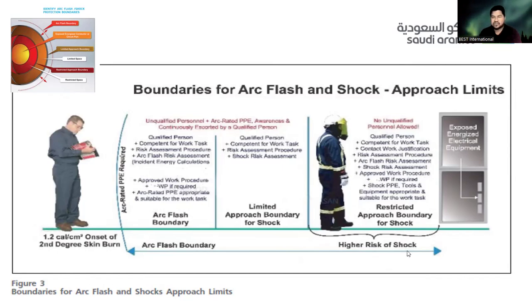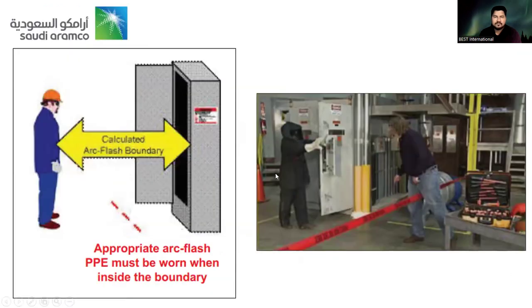There is an arc flash boundary and high risk of shock. See the PPE level here, where we have a high risk of shock because the person is directly exposed near energized electrical equipment. And this is a restricted approach boundary for sure. This is another self-explanatory one: we have to carefully define the line of fire, the boundary nobody should cross without a proper permit, proper PPE and guidelines, because in electrical systems there must be a procedure. The procedure should be shared and training must be conducted. Later, periodic inspections to evaluate effective implementation are also important.